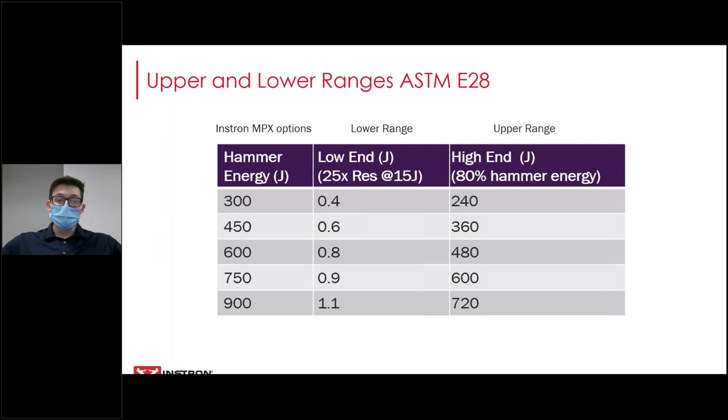So these ranges are examples. They've been verified through the Charpy NIST program, although the values of your upper and lower ranges will still need to be verified with each frame.